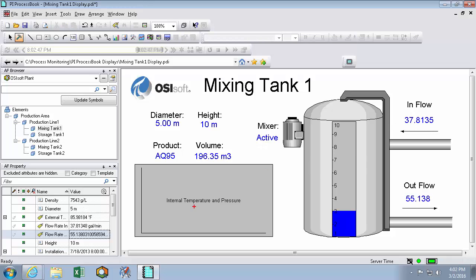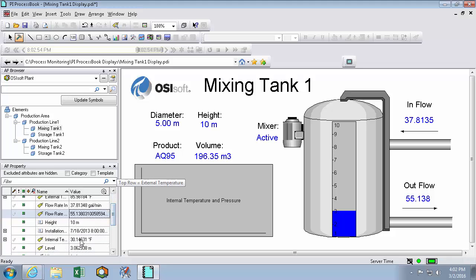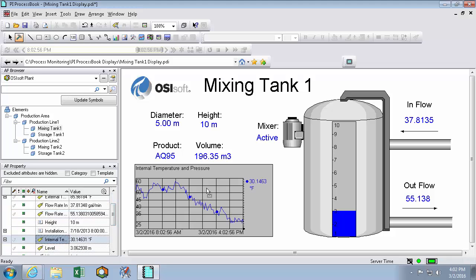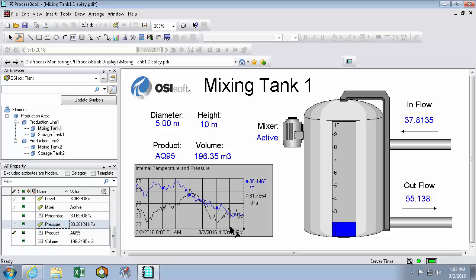And I can even do trends using this method. So here's my internal temperature and pressure trend. So what I'll do is find my internal temperature, drag it onto the trend, and then I'll find pressure, and then just stack it on top. And this trend will accommodate both those values.